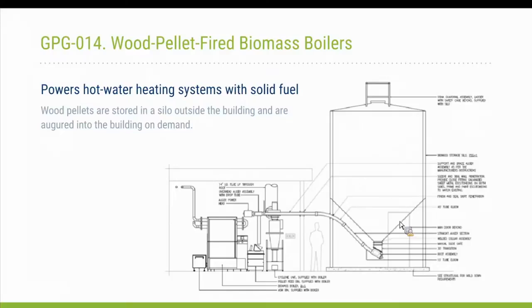Those pellets have, as you can see at the bottom of the silo, an auger - basically a small flexible screw conveyor that pulls the pellets out of the silo and runs them through the wall of the building. So the pellet and fuel storage is all outside. The pellets come through on an automated basis; these augers that feed the bins inside are automated. If there's a low level, it calls for more pellets and fills the bin up inside.